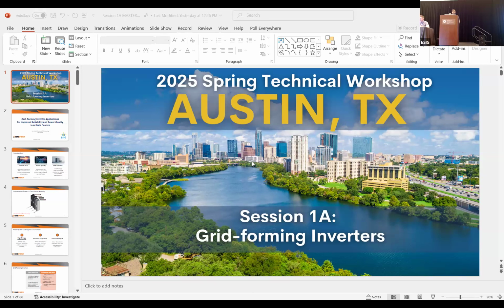So the reason why a specific value of frequency is not mentioned there is it can change depending upon whether this is a battery, whether this is a wind turbine, whether it's type 3 wind, type 4 wind. This cutoff frequency will depend upon all of those conditions. It will depend upon whether the battery is a 10 megawatt battery versus a 20 megawatt battery versus a 50 megawatt battery versus a 100 megawatt battery. It will depend upon whether the 100 megawatt battery is operating at 1 per unit, 0.9 per unit, 0.8 per unit, 0.7 per unit. It depends on all of that, because this relates to at that given operating point for that particular device, for that size of the device, how much damping can it provide to the system?